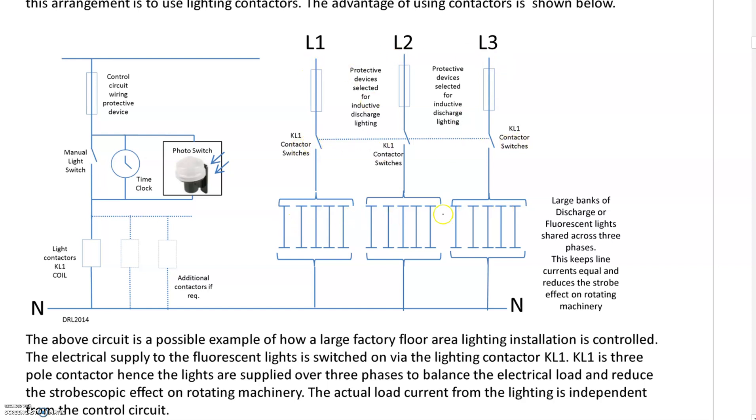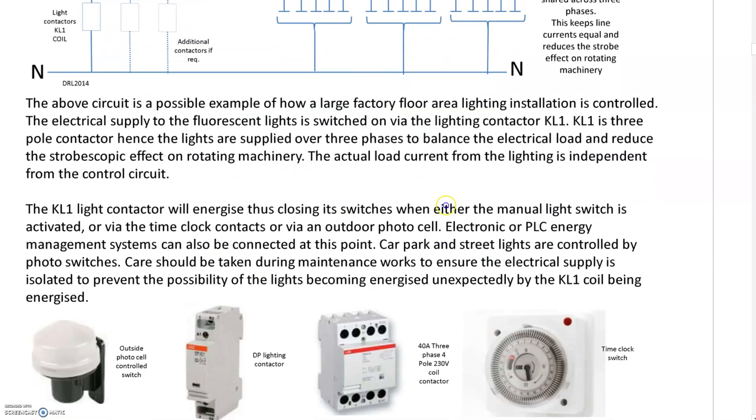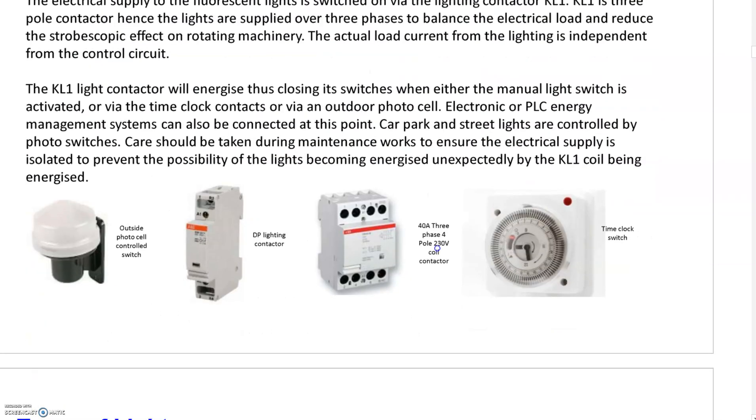On the three-phase supply there's a contactor L1, L2, L3, and these are banks of lights. When it's time to turn the lights on, the contactor pulls these contacts which energize the banks of lighting. This is what it looks like in the real: dawn-dusk sensor, modular contactor, three-phase three-pole contactor, and a time clock.